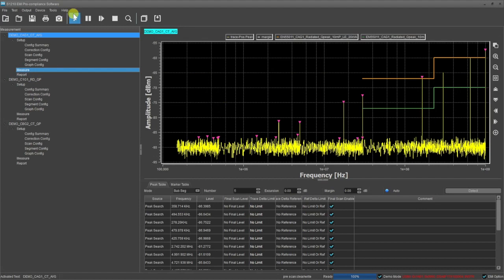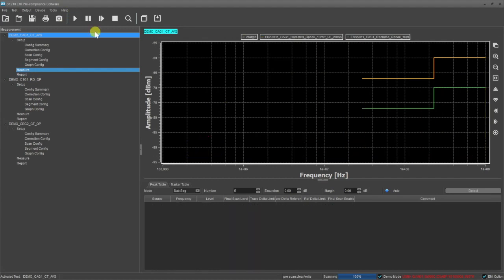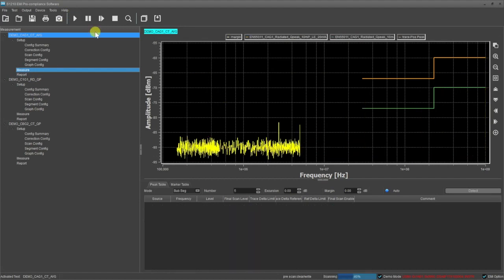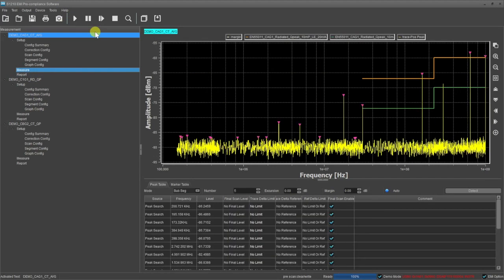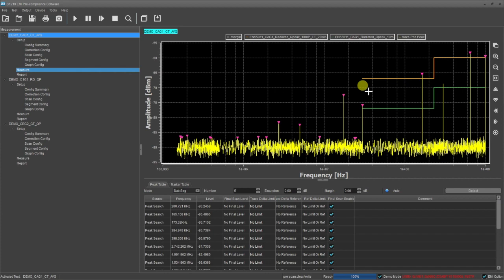Now let's go to the measurement. We have that all set up. We can go ahead and run our test. Here we see several peaks that are becoming close to the limit lines and some that are over the limit lines. Each of these can then individually be tested around that peak in a final scan mode that might give you more quasi-peak data or a closer look at the problem.